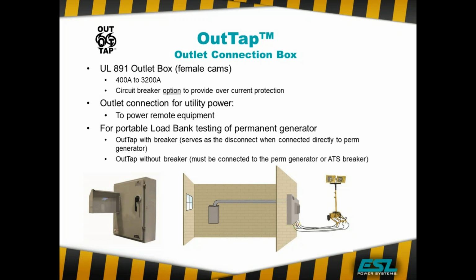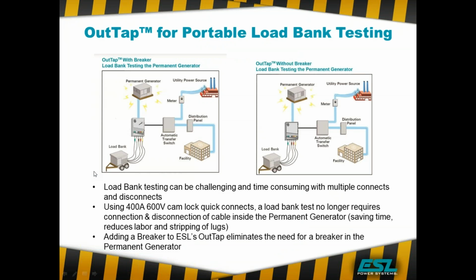So the Outtap, typically we do it with a breaker for load bank testing, but not always, can now be used to bring in your portable load bank and quick connect it into your permanent generator. So a very efficient, user-friendly way to assist your clients where they already have a means to back up the generator. Now they just need to load bank it.